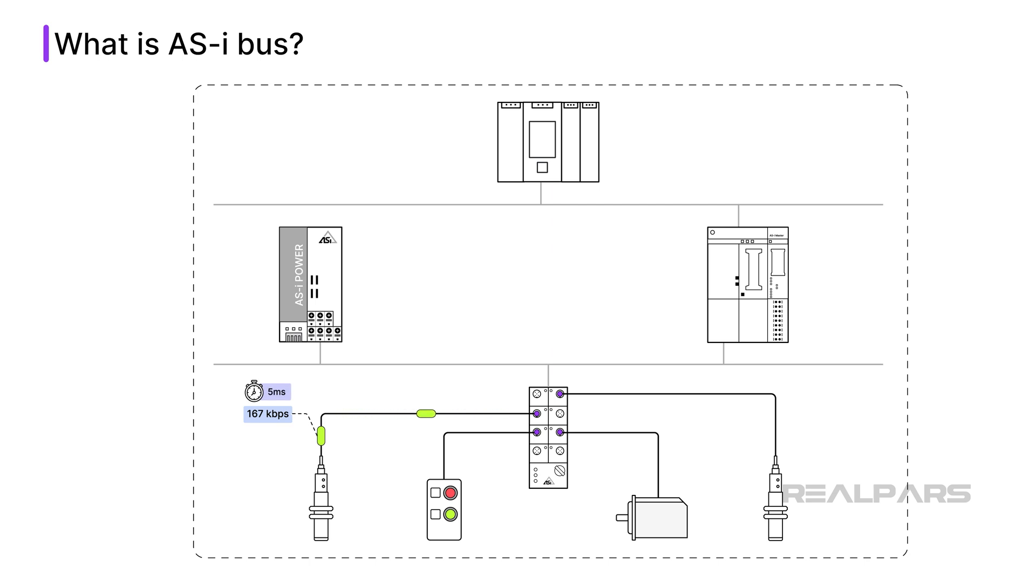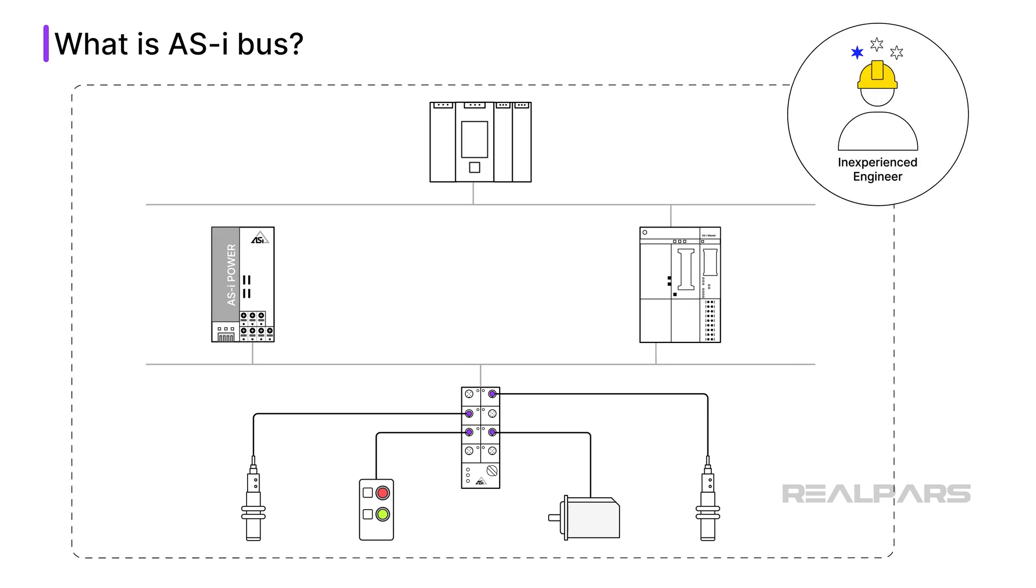Each standard AS-i bus slave device can receive 4 bits of data and send 4 bits of data. Because AS-i bus is so simple compared to Profibus PA or Foundation Fieldbus, even engineers new to automation field buses can design and set up an AS-i bus network.